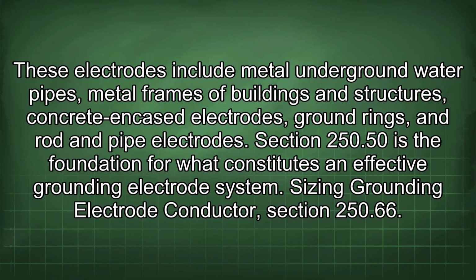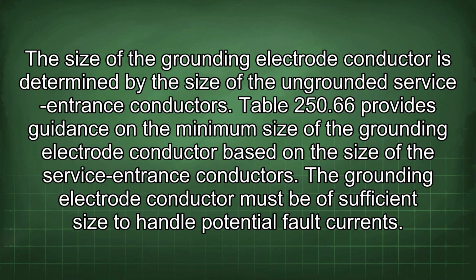Sizing grounding electrode conductor, section 250.66. The size of the grounding electrode conductor is determined by the size of the ungrounded service entrance conductors. Table 250.66 provides guidance on the minimum size of the grounding electrode conductor based on the size of the service entrance conductors. The grounding electrode conductor must be of sufficient size to handle potential fault currents.